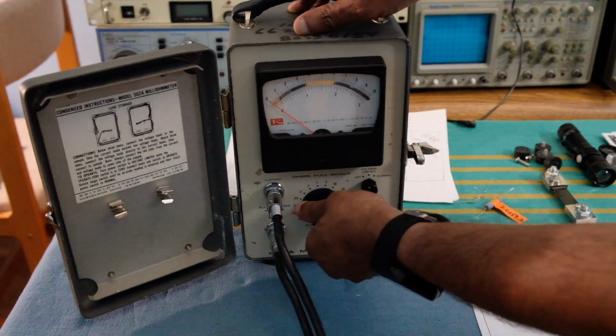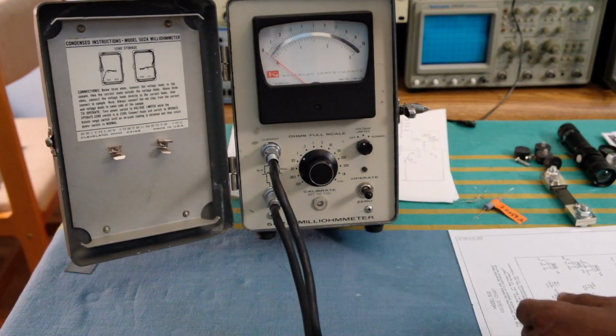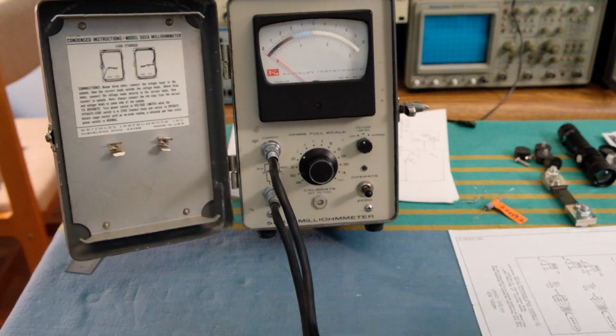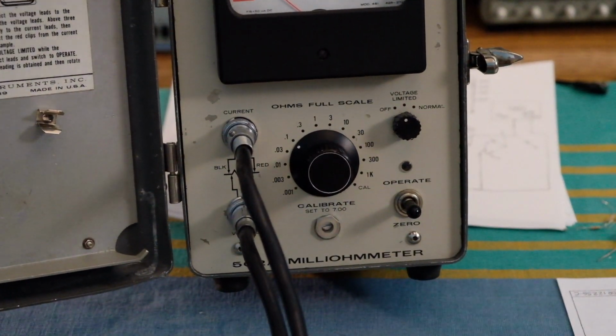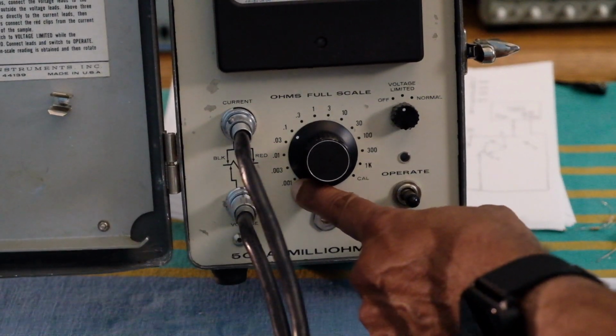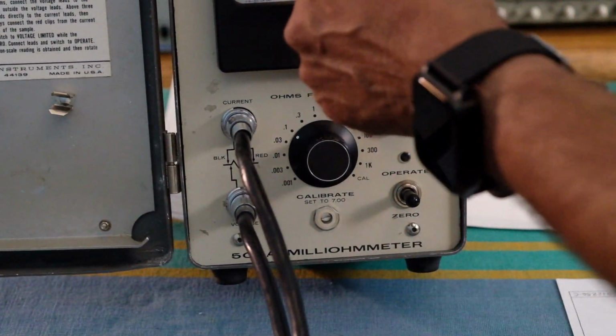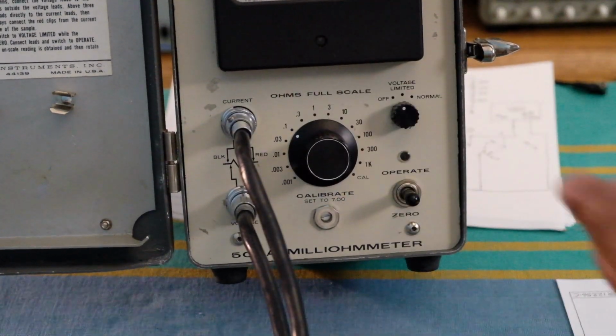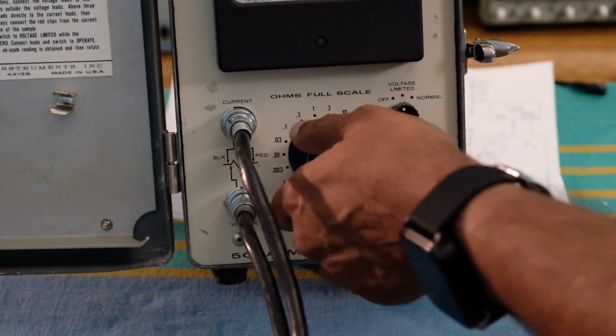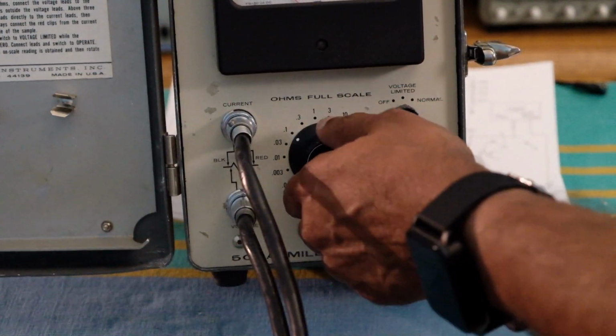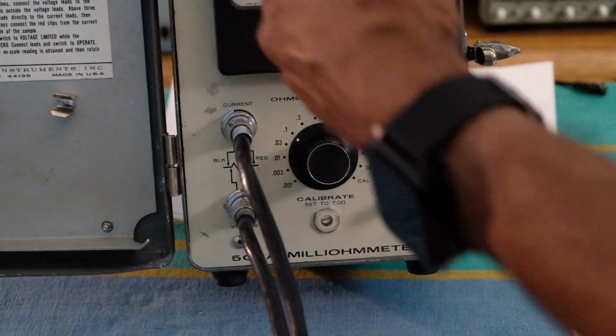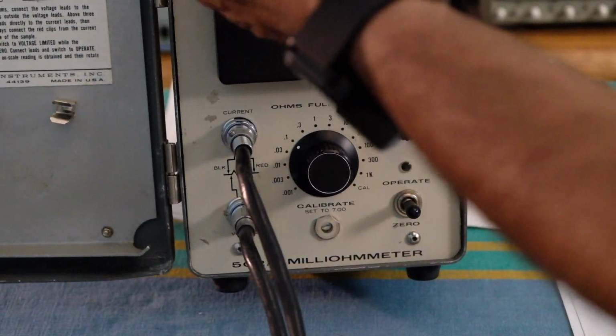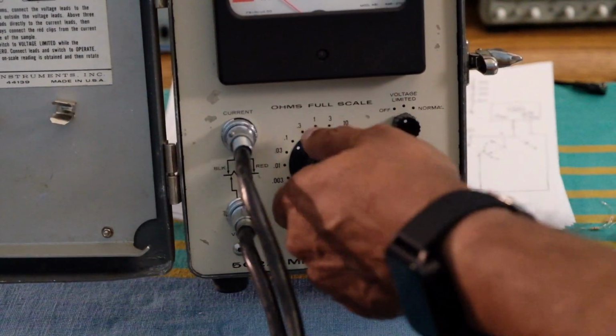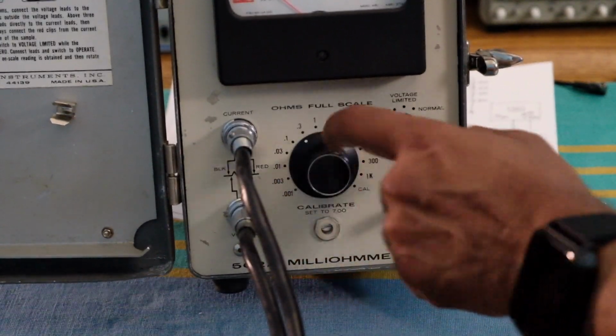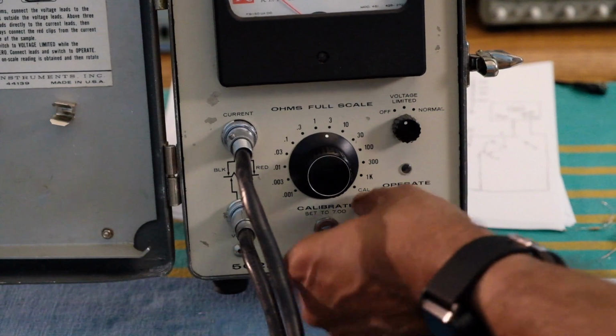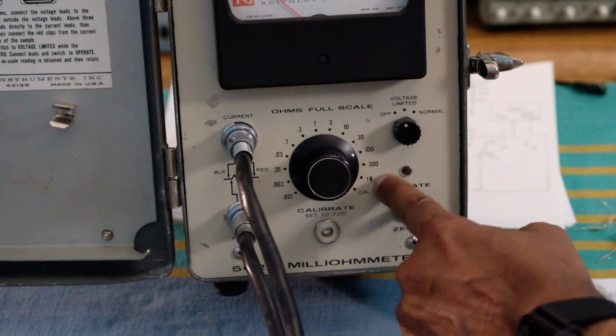And this is the main knob which sets the range, as you can see over here. I'm not sure if you can see this clearly, but try and zoom in. You can see that it goes to 0.001, 1 milliohm full scale. That means these fine ticks can be around 30 microohms, but I think down at the bottom of the scale it's got some offset, so I wouldn't worry. I wouldn't trust anything below like 100 microohms or so. So anyway, that goes up to 3. So here's where the upper range starts, 3, 10, 30 on the way all the way to 1K.